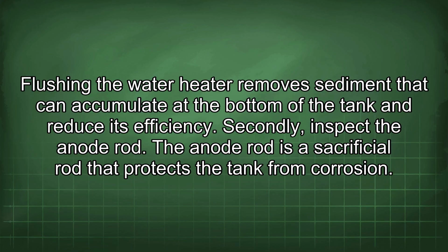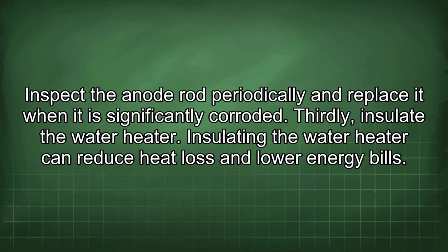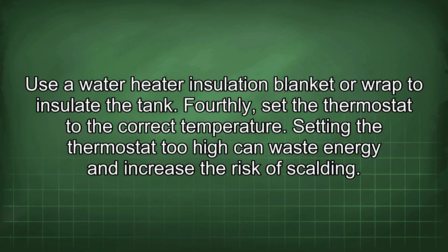Secondly, inspect the anode rod. The anode rod is a sacrificial rod that protects the tank from corrosion. Inspect the anode rod periodically and replace it when it is significantly corroded. Thirdly, insulate the water heater. Insulating the water heater can reduce heat loss and lower energy bills. Use a water heater insulation blanket or wrap to insulate the tank.